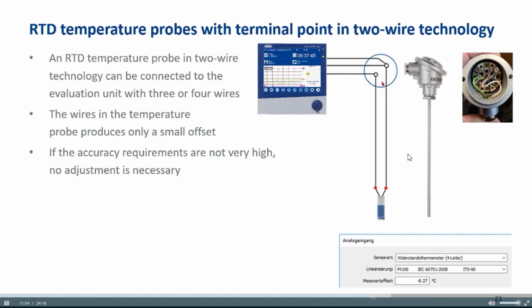Make it as follows. Let's say, okay, here I have my terminal point. And then please use 3 wires here. Normally, then it's absolutely okay. Then for these 30 meters, you have no offset. You have only this little offset here because of the 2 wires in your probe. But normally it's very short. Maybe you have only a few millikelvin or 0.1 Kelvin, something like this. So the offset will be very small.